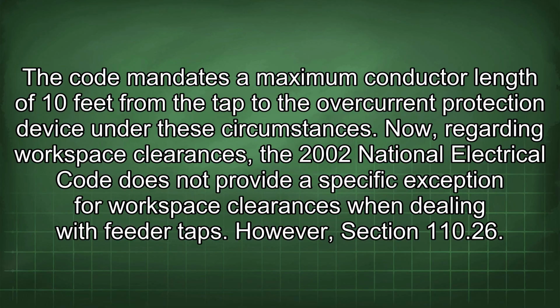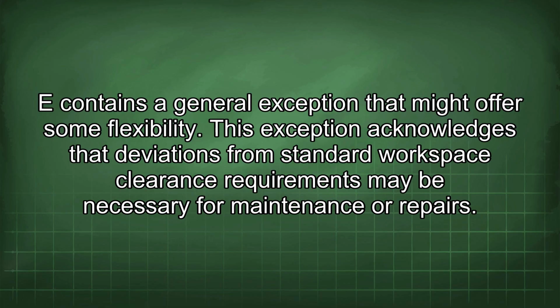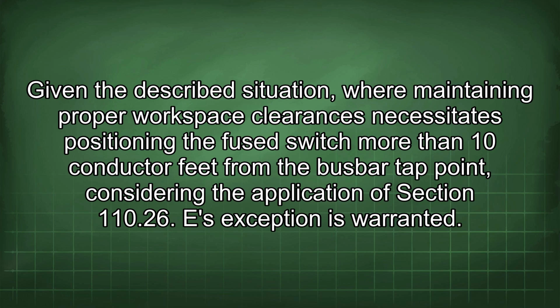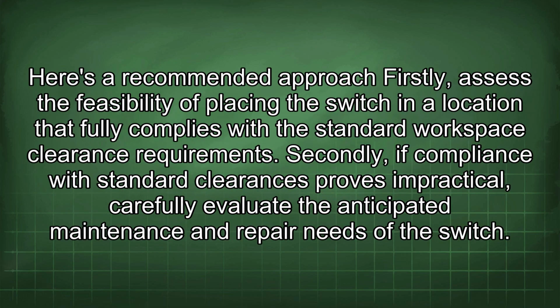circumstances. Now, regarding workspace clearances, the 2002 National Electrical Code does not provide a specific exception for workspace clearances when dealing with feeder taps. However, Section 110.26(E) contains a general exception that might offer some flexibility. This exception acknowledges that deviations from standard workspace clearance requirements may be necessary for maintenance or repairs. Given the described situation where maintaining proper workspace clearances necessitates positioning the fused switch more than 10 conductor feet from the busbar tap point, considering the application of Section 110.26(E)'s exception is warranted. Here is a recommended approach.